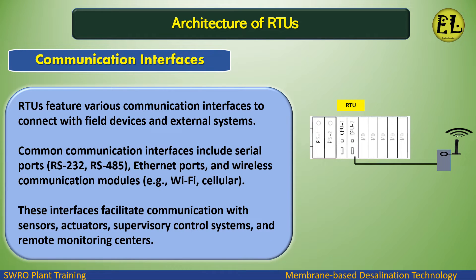RTUs feature various communication interfaces to connect with field devices and external systems. Common communication interfaces include serial ports (RS-232, RS-485), Ethernet ports, and wireless communication modules such as Wi-Fi and cellular. These interfaces facilitate communication with sensors, actuators, supervisory control systems, and remote monitoring centers.